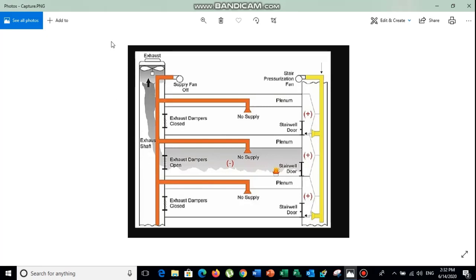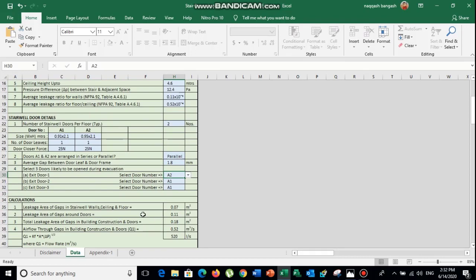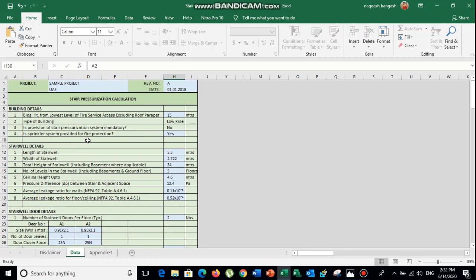Now we will check how to calculate the required airflow for staircase pressurization. Here is a sample Excel sheet. This is the building height from the lowest level of fire service access including roof parapet — I am using 15 meters because I have a low-rise building of almost 15 meters. The provision of stair pressurization system is mandatory — yes or no — it defaults to no. You also choose whether a sprinkler system is provided for fire protection — yes or no. I am selecting yes.